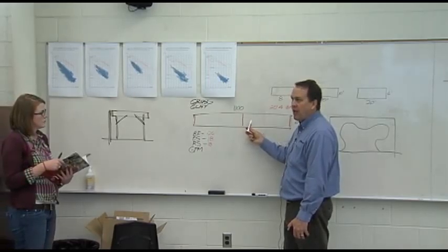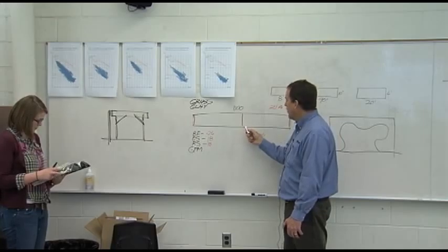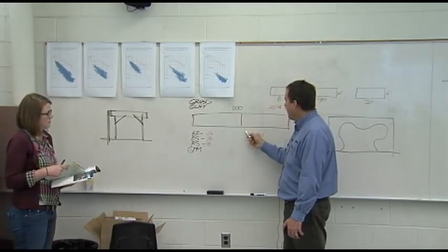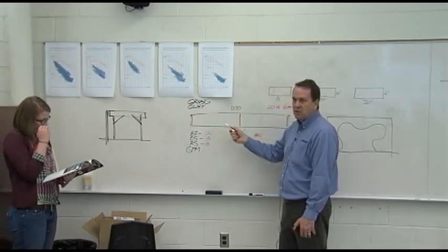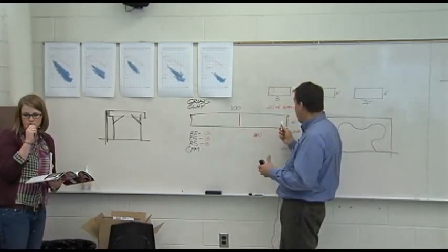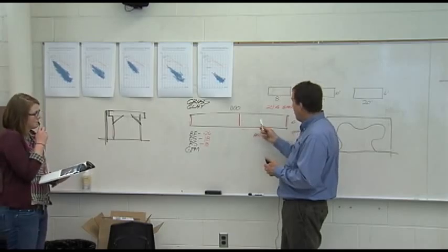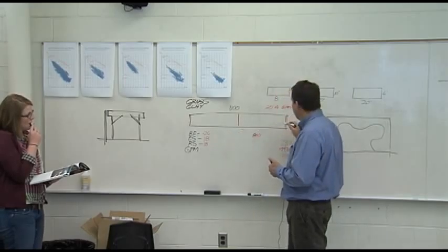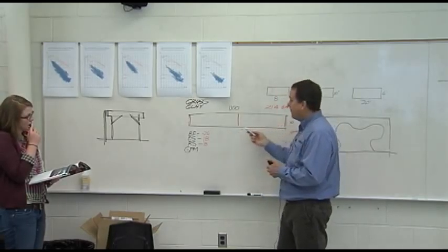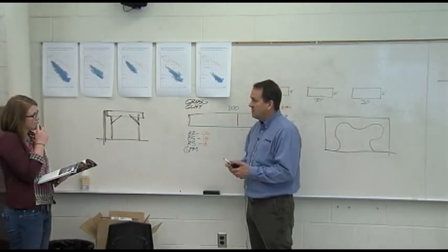this pipe to handle the flow rate for this entire zone, we can go 840 feet that direction and 840 feet that direction. So we'll have a center feed header here and then an exhaust header here. And on both of these exhaust headers, we will put a flush valve. Okay?